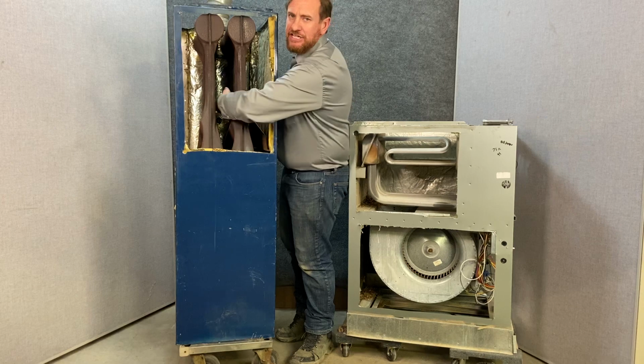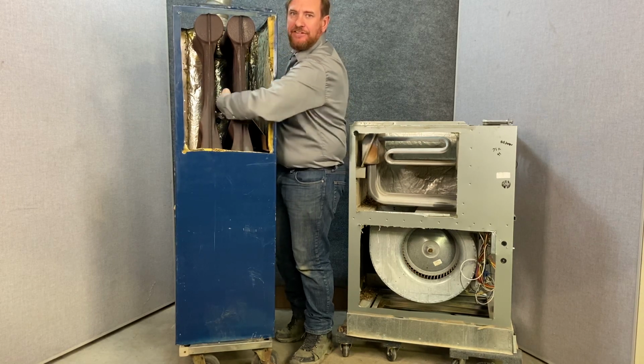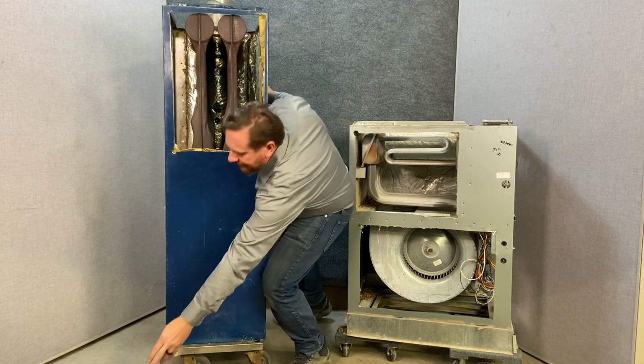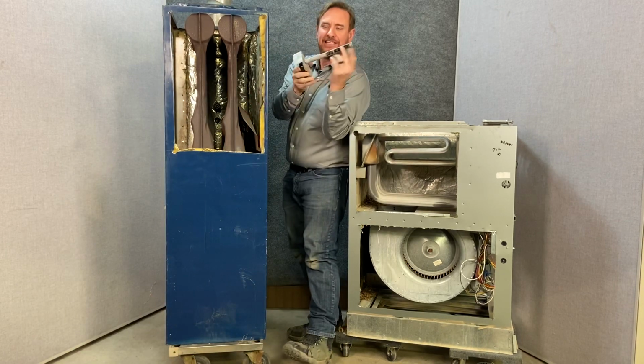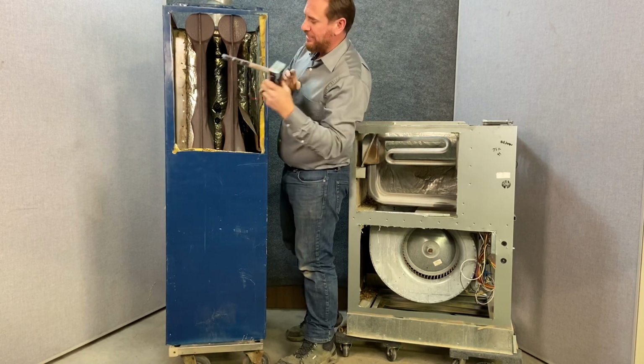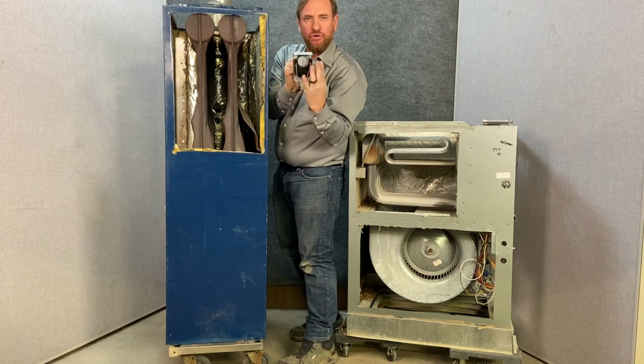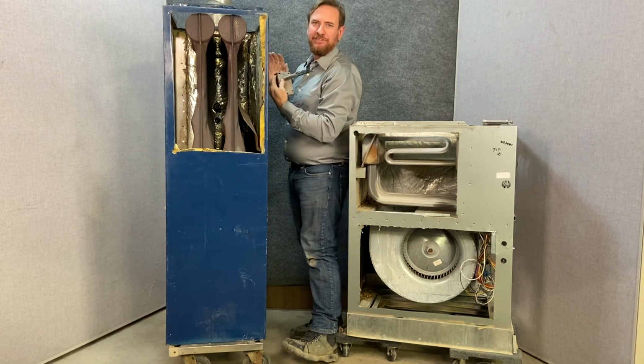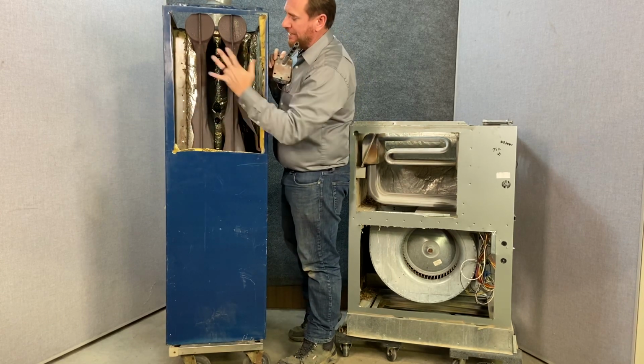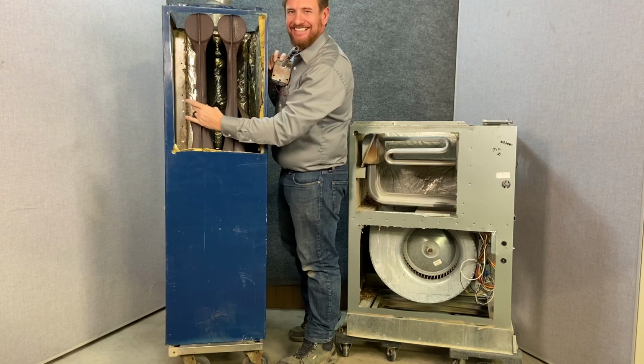Between these 2 heat exchangers, if I was reaching my hand in here, I could feel this fan limit switch. So this side of the fan limit switch is between this heat exchanger, like so. The control side that you see is on the opposite side of that heat exchanger. So this is where the air from the house goes and the flames burn inside of here.